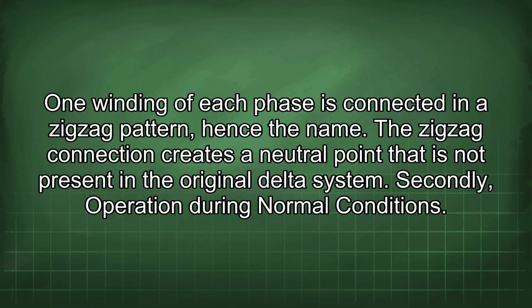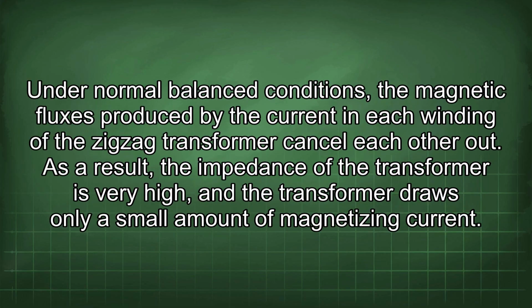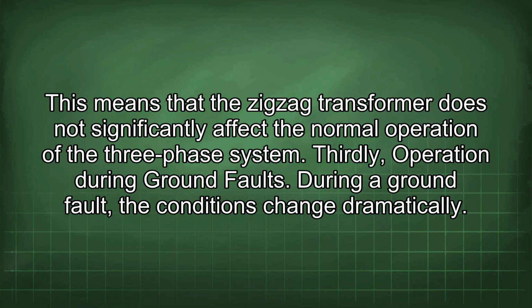Secondly, operation during normal conditions. Under normal balanced conditions, the magnetic fluxes produced by the current in each winding of the zigzag transformer cancel each other out. As a result, the impedance of the transformer is very high, and the transformer draws only a small amount of magnetizing current. This means that the zigzag transformer does not significantly affect the normal operation of the three-phase system.